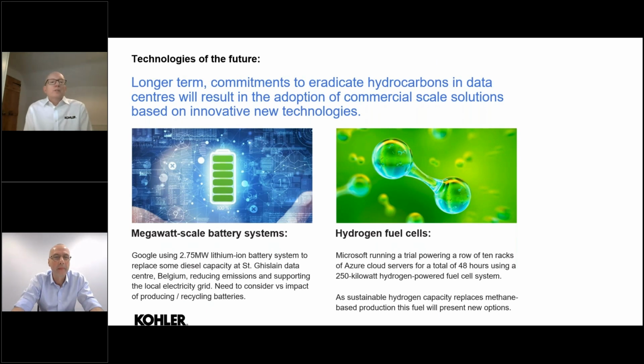So what are the technologies for the future? Longer-term commitments to eradicate hydrocarbons in data centres will result in the adoption of commercial scale solutions based on newer technologies. We've seen installations of megawatt scale battery systems such as Google, where they installed a 2.75 megawatt lithium ion battery system, and that did replace some of the standby generators. Whilst it reduced the emissions, it was also used to support the local electricity grid. But we need to consider in these types of installations the impact of producing and recycling of batteries.